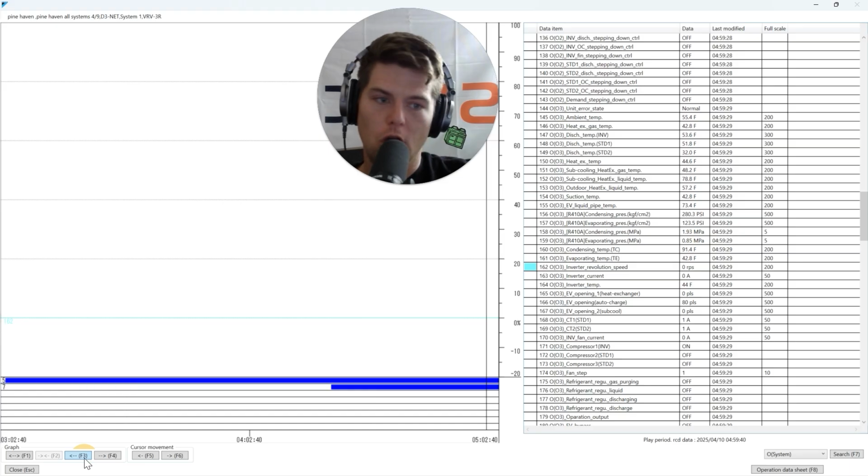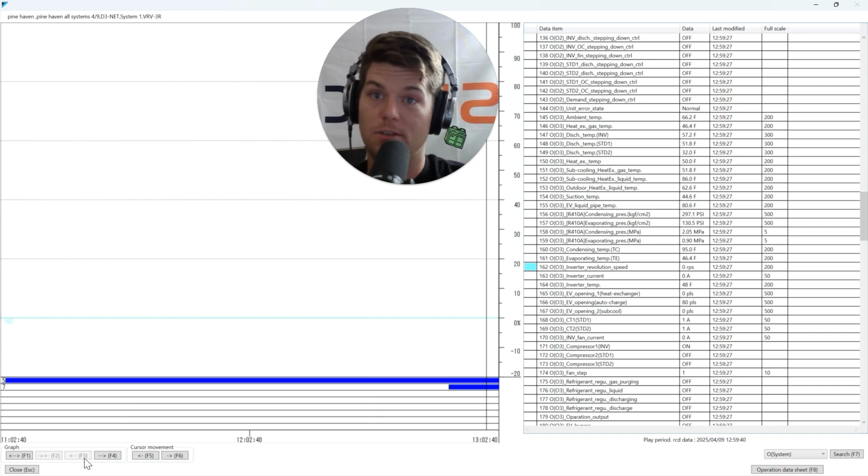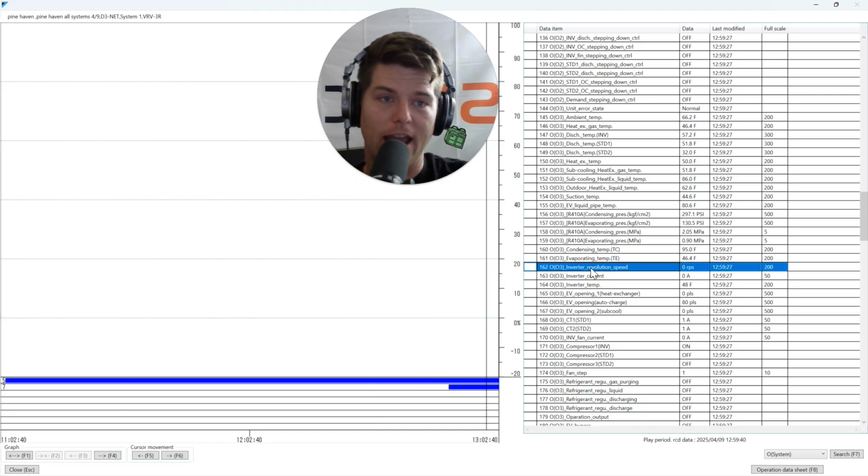And again, sure, in low load situations where maybe only one module runs, maybe not. But remember, outdoor rotation is a thing. And so the units are designed to evenly wear compressors. We've talked about that in other videos. If I see a compressor like this that never turns on, I know that this third chassis, this triple module system, the last module, sub 2 module, third module, number 3, is locked out. It's closed. Okay, so knowing VRV3, and we know this is locked out now because I just showed you and I proved it to you.